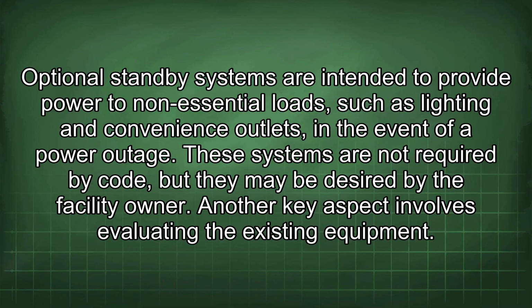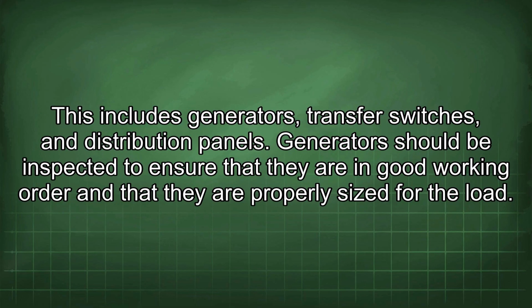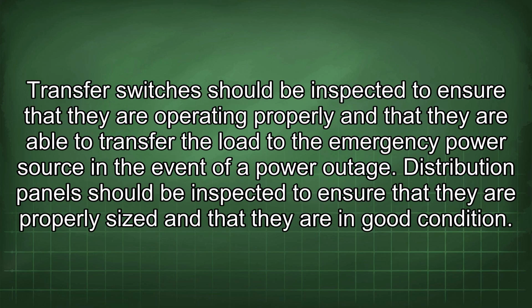Another key aspect involves evaluating the existing equipment. This includes generators, transfer switches, and distribution panels. Generators should be inspected to ensure that they are in good working order and that they are properly sized for the load. Transfer switches should be inspected to ensure that they are operating properly and that they are able to transfer the load to the emergency power source in the event of a power outage. Distribution panels should be inspected to ensure that they are properly sized and that they are in good condition.